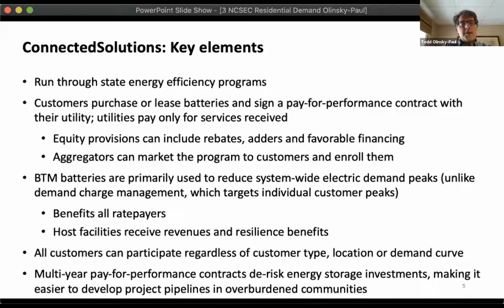Once the program is in place, the behind-the-meter batteries are primarily used to reduce system-wide electric peaks. This is a little different from a demand charge management approach, where a battery would be used by a commercial customer to reduce their own facility peak. In this case, the batteries are being used to address the system peaks.